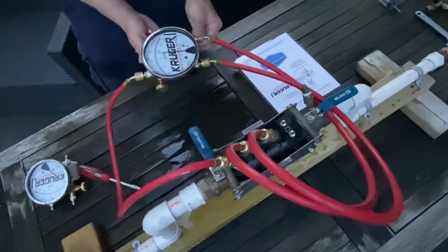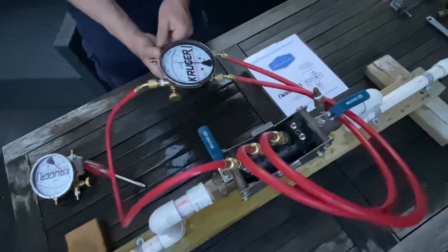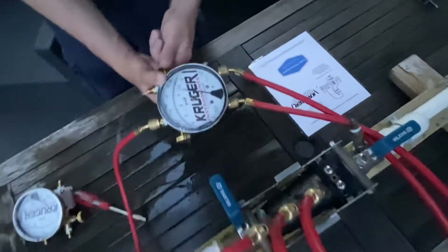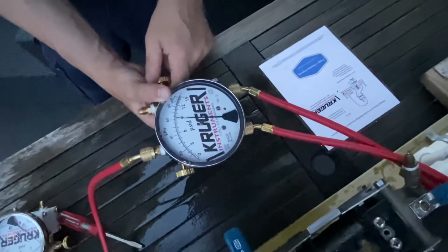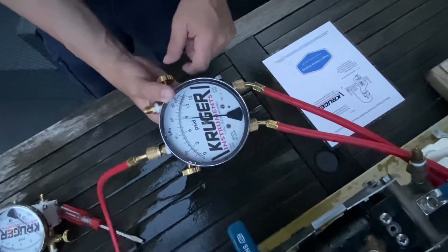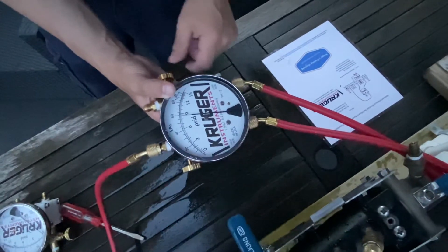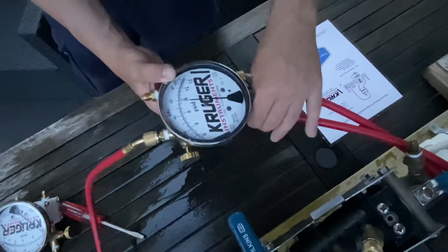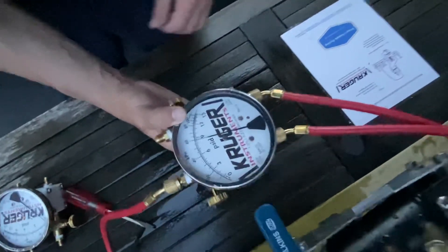Then you want to get the tightness of check valve one. So you open low bleed, close low bleed, get that correct reading. It's jumping because of the pressure fluctuations, so the reading is about 8.4.